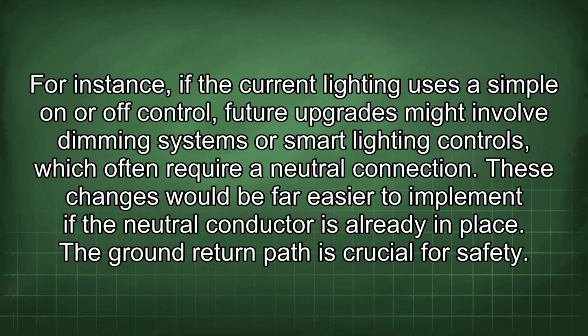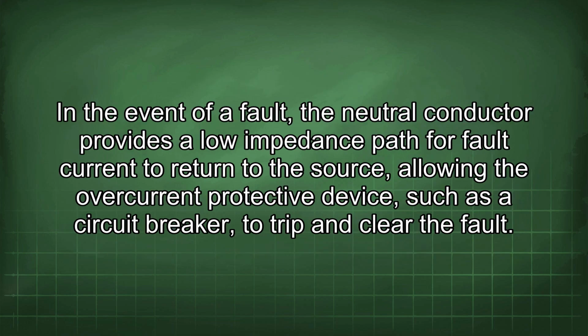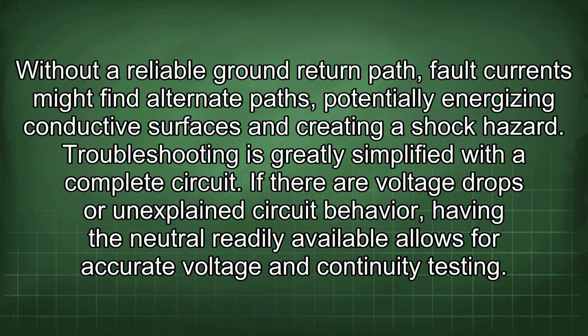The ground return path is crucial for safety. In the event of a fault, the neutral conductor provides a low impedance path for fault current to return to the source, allowing the overcurrent protective device, such as the circuit breaker, to trip and clear the fault. Without a reliable ground return path, fault currents might find alternate paths, potentially energizing conductive surfaces and creating a shock hazard.